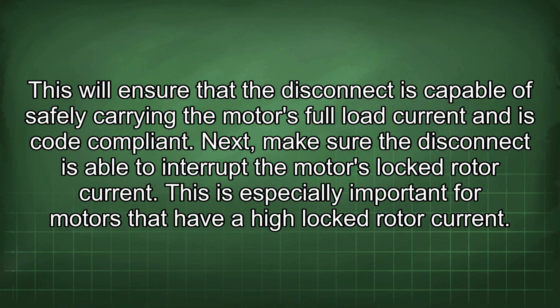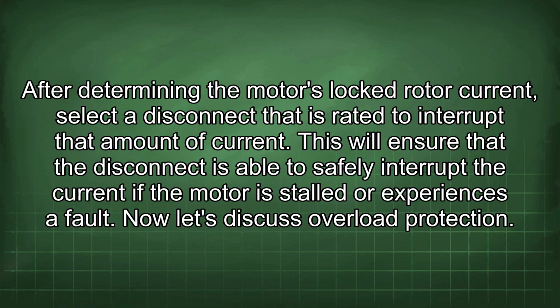This is especially important for motors that have a high locked rotor current. After determining the motor's locked rotor current, select a disconnect that is rated to interrupt that amount of current. This will ensure that the disconnect is able to safely interrupt the current if the motor is stalled or experiences a fault. Now let's discuss overload protection.